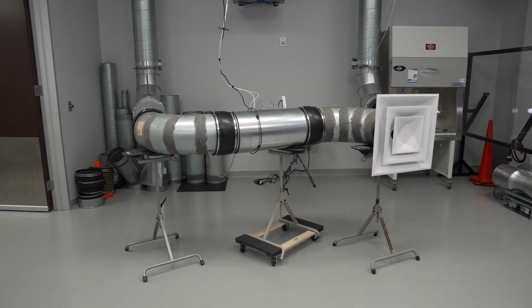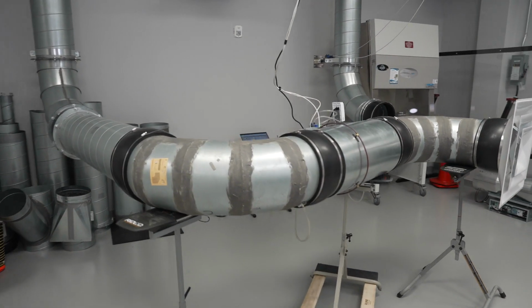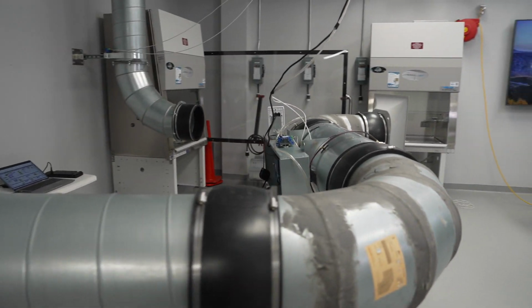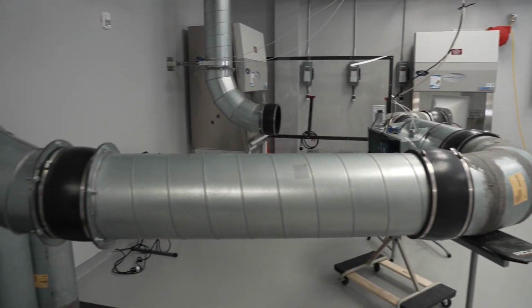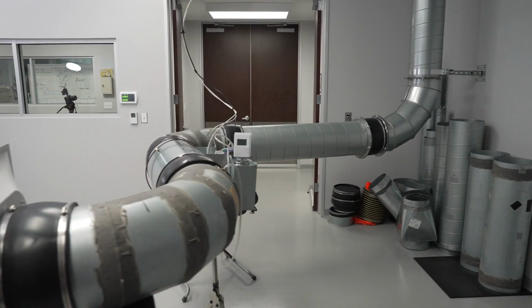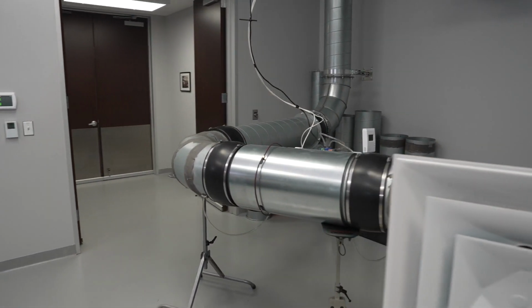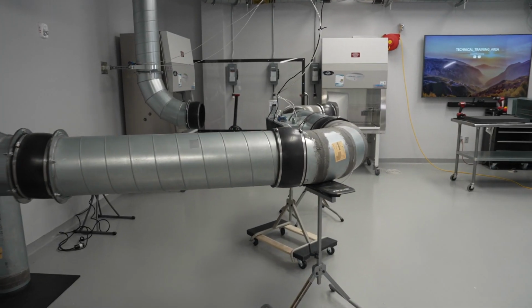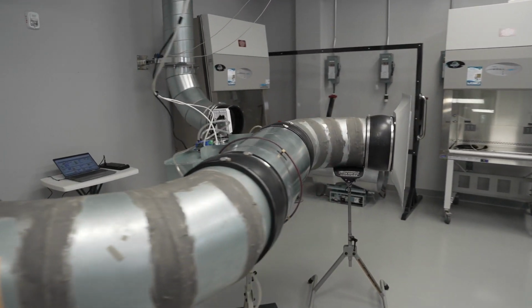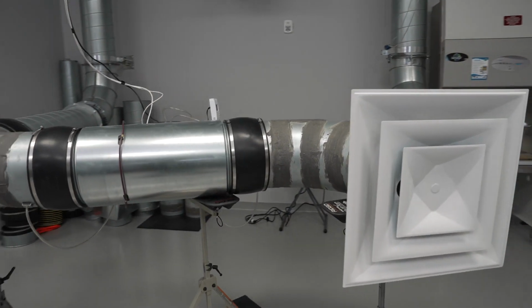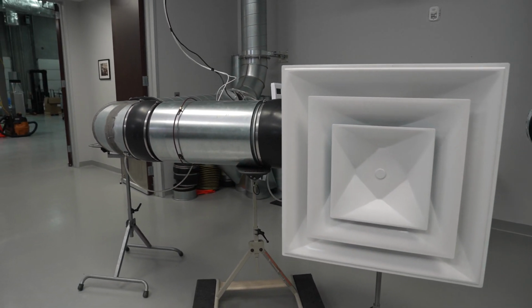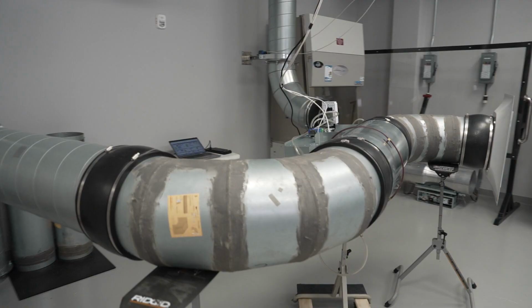When the 12-inch round SAV with the normal calibration curve was tested, it performed to within plus or minus 4% accuracy from 2,500 feet per minute to 150 feet per minute and plus or minus 6 feet per minute accuracy below 150 feet per minute, including with upstream and downstream elbows. The SAV ductwork can be sized to between 1,000 and 1,500 FPM max flow, eliminating the need for acoustical abatement, operating at a low pressure drop leading to a low energy use intensity with no internal insulation required for acoustical abatement, leading to superior indoor air quality.